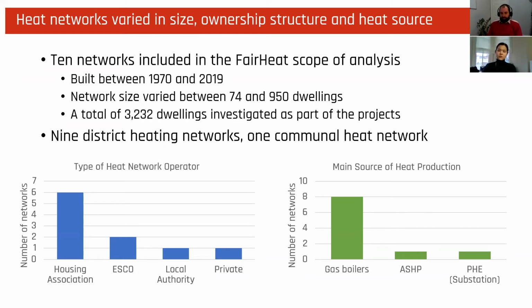We also covered a broad range of heat network operators. So we wanted to make sure we covered social housing associations and local authorities, but also the private market, so private developers and ESCOs. And for the main heat production, these are legacy systems, so unsurprisingly gas boilers were dominant. There was one air source heat pump project and one that was actually fed off an existing district heating system, so it had a plate heat exchanger.